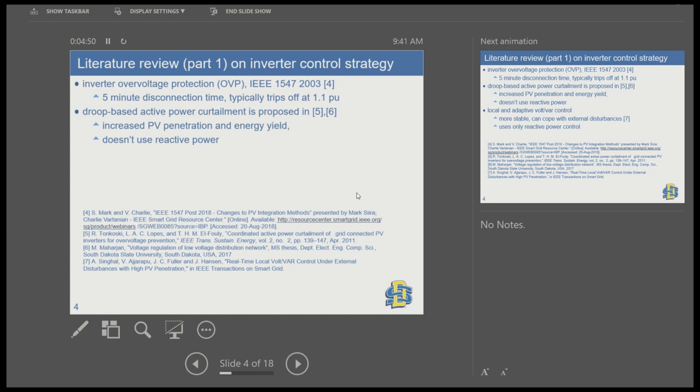Another approach is a droop-based active power curtailment approach, proposed in references 5 and 6. In droop-based active power curtailment, you curtail based on your voltage deviation from some critical value. You do not curtail all at once but gradually, so you don't have to remain disconnected for 5 minutes. However, it does not use reactive power, meaning we can expect high energy curtailment.